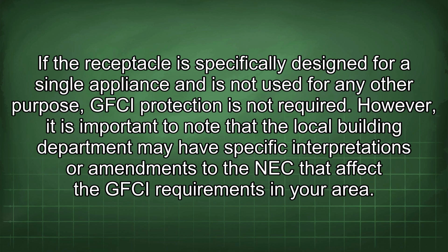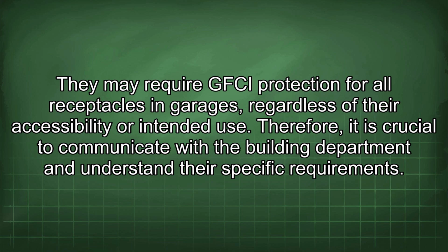However, it is important to note that the local building department may have specific interpretations or amendments to the NEC that affect the GFCI requirements in your area. They may require GFCI protection for all receptacles in garages, regardless of their accessibility or intended use. Therefore, it is crucial to communicate with the building department and understand their specific requirements.